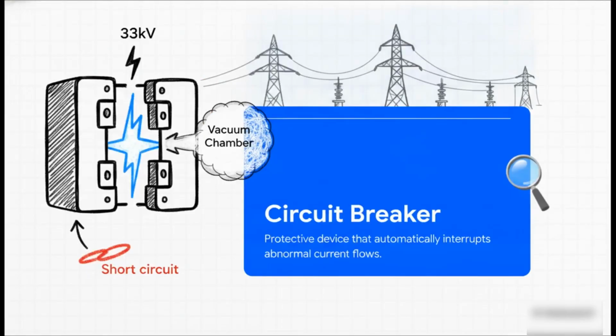So you might be asking, if the isolator can't break a live current, what actually does? The answer is the circuit breaker. Unlike the manual isolator, a circuit breaker is a highly advanced automated switch. If there's a huge fault like a short circuit, the circuit breaker is designed to safely and instantly break the live circuit. For example, vacuum circuit breakers actually use a vacuum chamber to immediately suffocate and extinguish the massive electrical arc that tries to form when you suddenly snap a live 33 kV line.